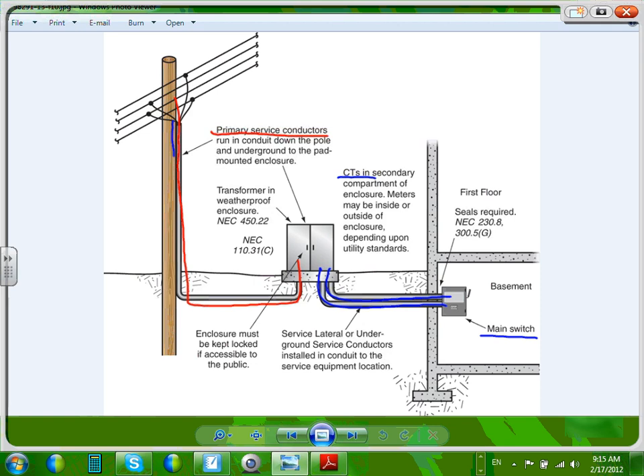You can see with CT cabinets, you're going to have your CT cabinet here with a transformer, and you come in. I would say 90% of the time, commercially, that's what you're looking at. Any comments? And that's what you guys did with me, right? You put your CT cabinet outside, you brought the cable from the utility transformer to the CT cabinet into the building. Okay, who owns what?